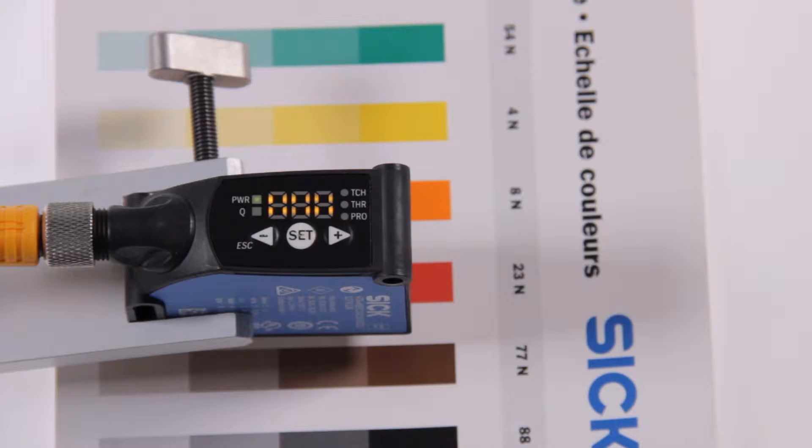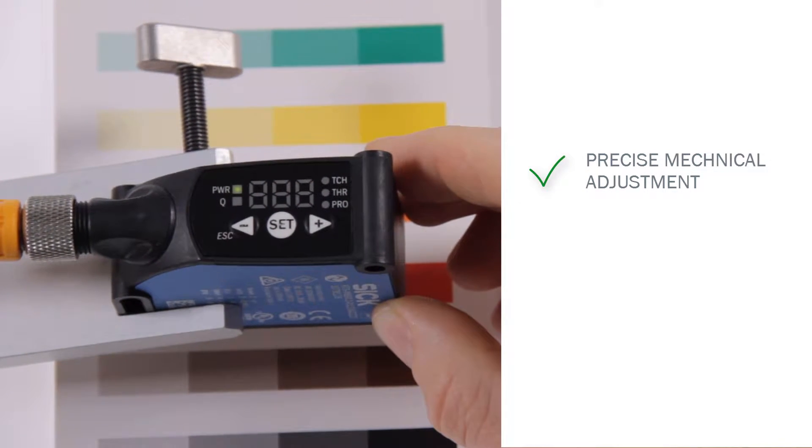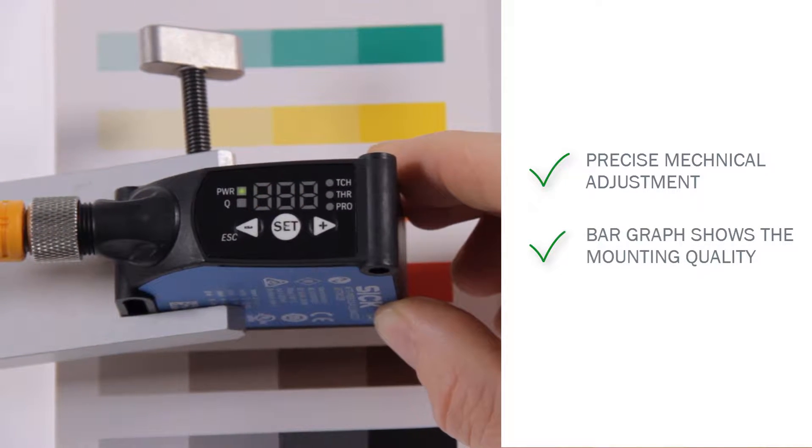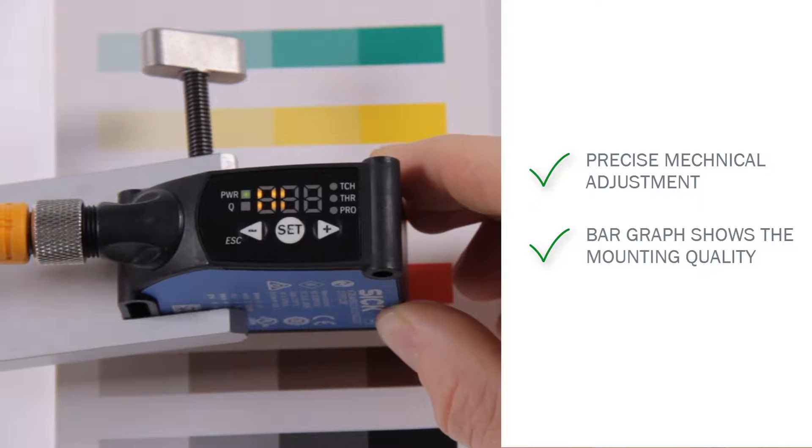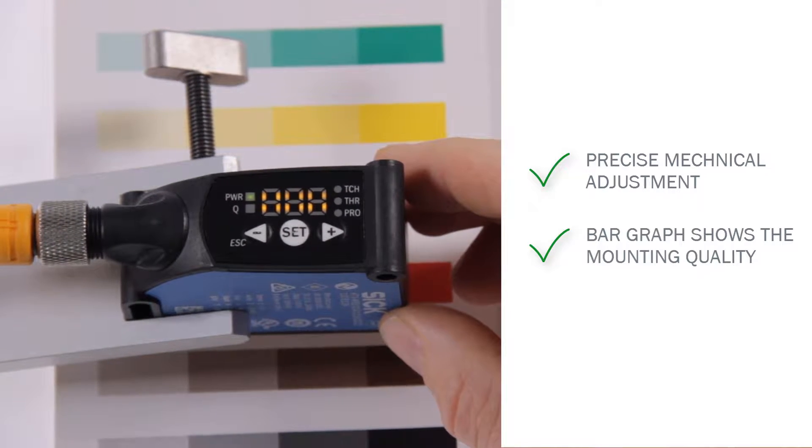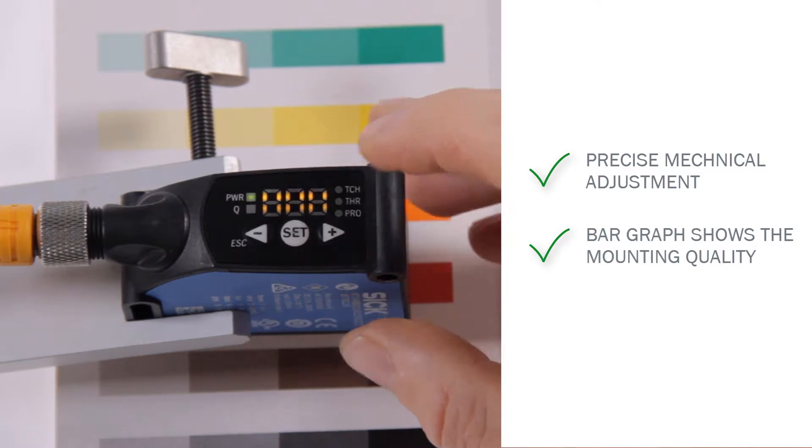Mounting feedback. When setting up the sensor for the first time, the so-called mounting feedback is active. This function allows a precise mechanical adjustment regarding sensing distance of the sensor. The bar graph shows the mounting quality. The more bars are shown, the better the mounting and sensing distance. When the adjustment is done, finish the procedure by pressing SET.